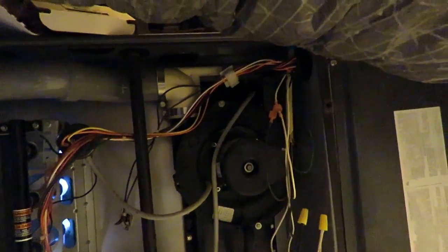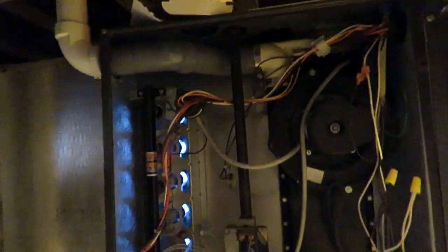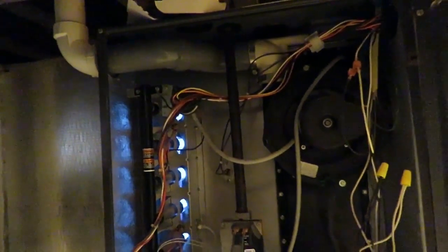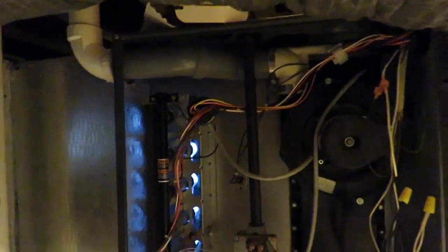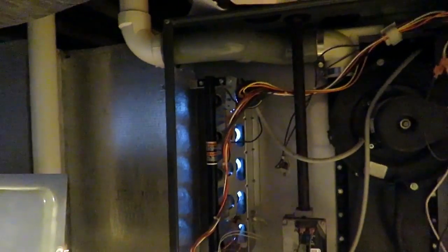Here we are inside the unit. Fans working, a little bit noisy, noisier than we normally like to see. We have no real rust to speak of. The heat exchanger is there. Flames are relatively blue, a little bit of orange in them, but nothing critical. There is no service tag on the unit, so we don't know when the last time it was serviced. We're certainly going to have somebody look at it. We'll see what else we find as we go along.